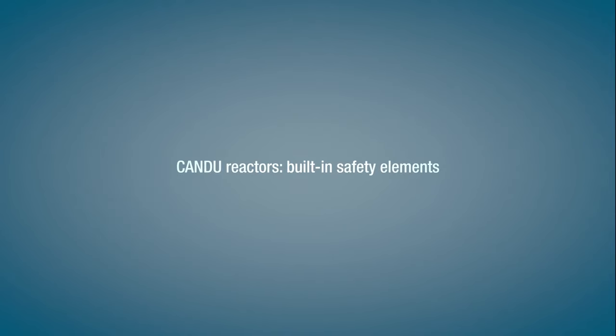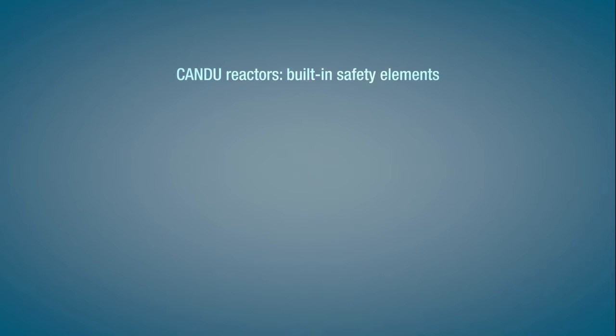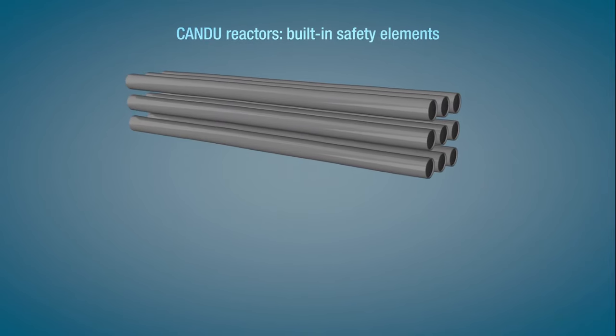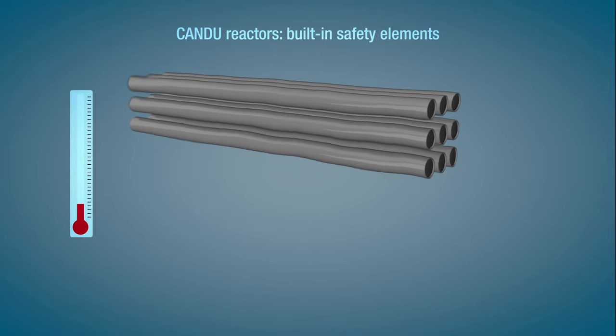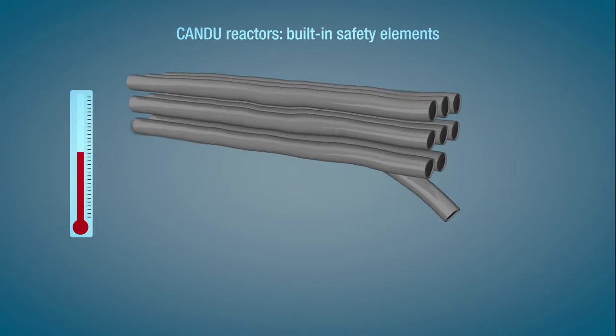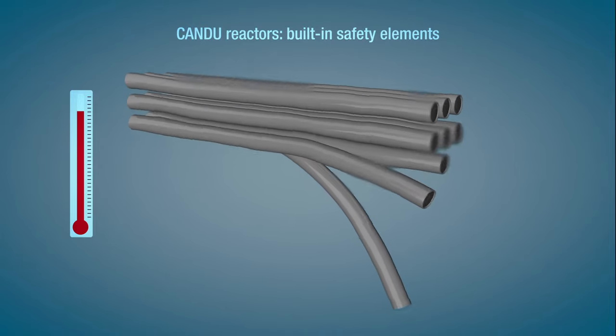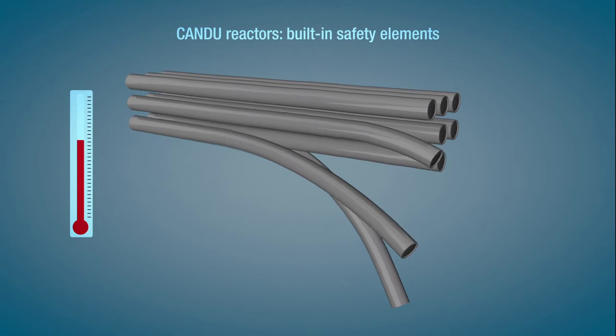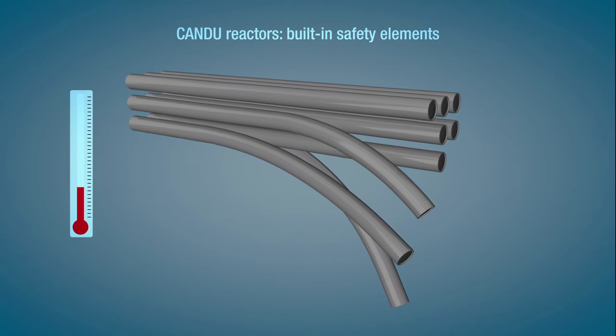CANDU reactors also have many automated safety elements built in. The fuel channels themselves can only maintain the nuclear reaction process if they are mechanically sound. Should temperatures start to increase abnormally, these fuel channels will start to deform and bend due to gravity, instantly reducing the efficiency of the reaction and cooling the reactor.